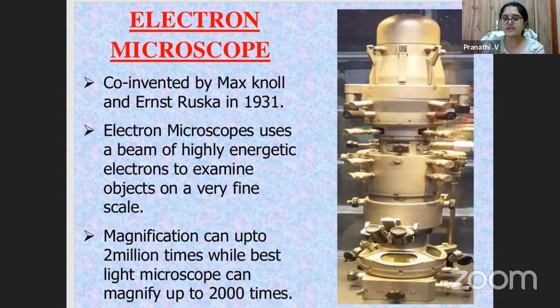Maintenance and cleaning of the microscope also make quite a bit of impact on the image that you are viewing. And of course, if you are measuring, for example, a pollen grain or yeast budding cells, there will be differences in the sizes according to how the microscope is maintained. And if you don't calibrate properly, you will definitely get a wrong image and wrong measurement.